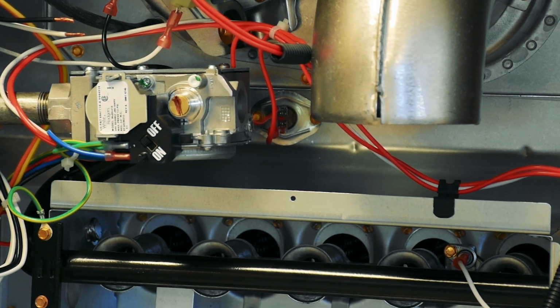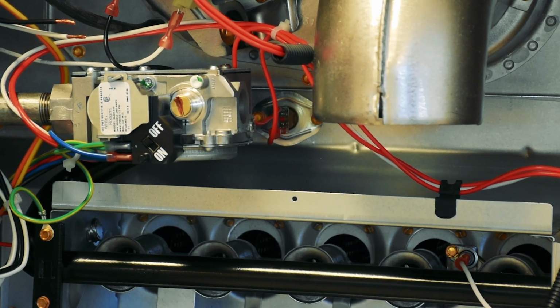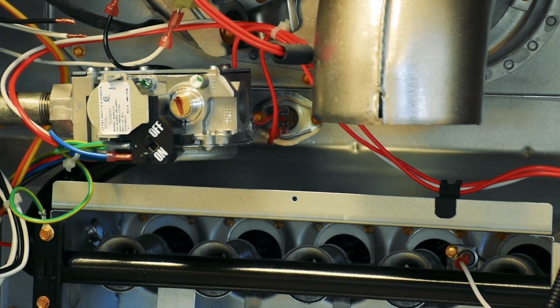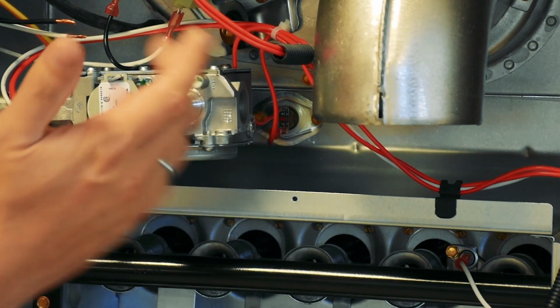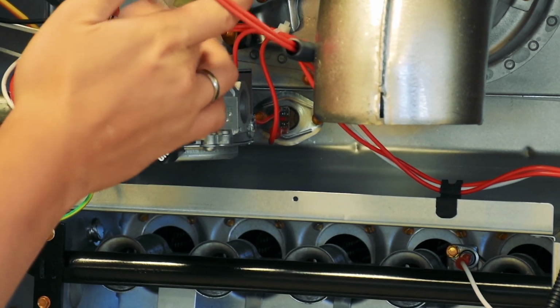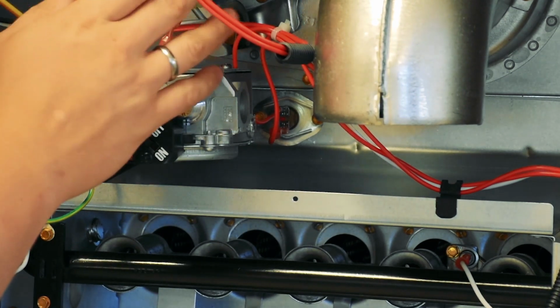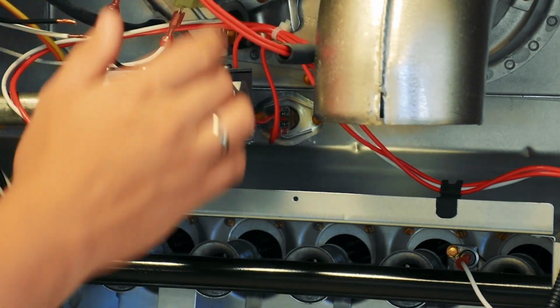It will heat your house, and when the thermostat reaches the needed temperature, for example, you set your heat to 75 Fahrenheit, the thermostat will cut off the circuit between W and R. What will happen? It will shut down the power to the gas valve, because here's the heating 24 volts actually. Sometimes it shuts down the inducer motor immediately, but normally it should run a little bit, probably 10-15 seconds, and then the inducer motor turns off too.